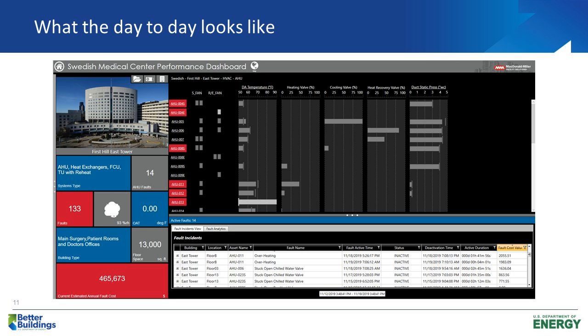We also see a quick view of all the different air handlers, which could be on different platforms or control systems—in this case, I believe these are all Johnson Controls units at this building. We see a live snapshot of units with active faults in red, the statuses of the fans, temperatures versus set points, valve positions, and static pressures versus their set points. Below that, we see the individual fault incidents listed.